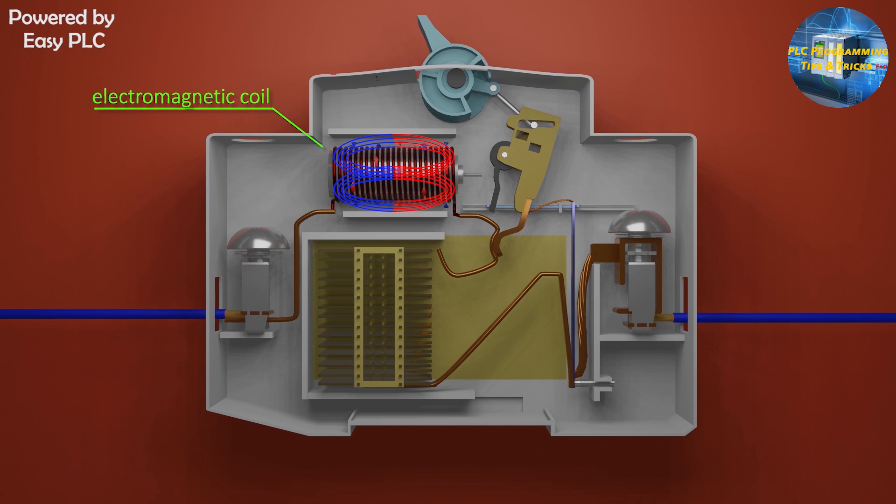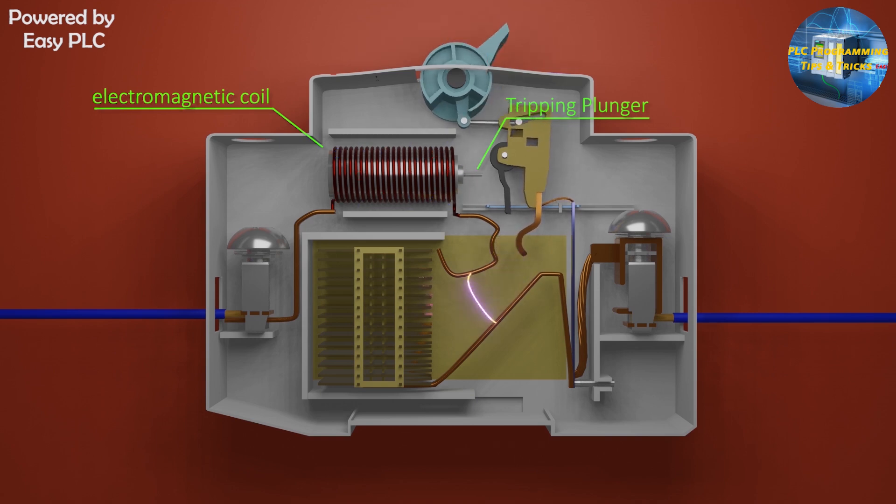But in the case of the short circuit on the load side, a large current passes through the coil and it produces a very large and strong magnetic field around the coil. Because of this magnetic field, the plunger inside the coil moves outwards and hits the tripping mechanism. You can see that the tripping lever is in the black color. Because of this action the operating mechanism moves backwards and MCB trips and cuts the current path.